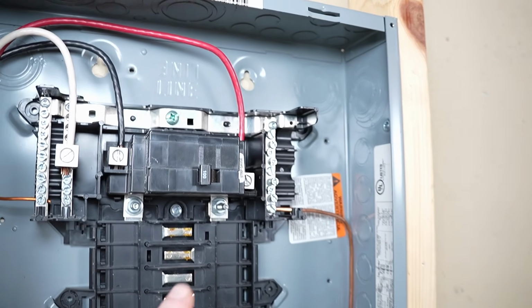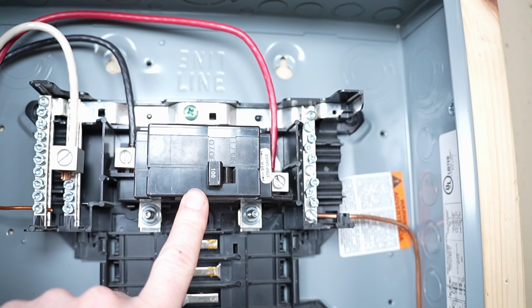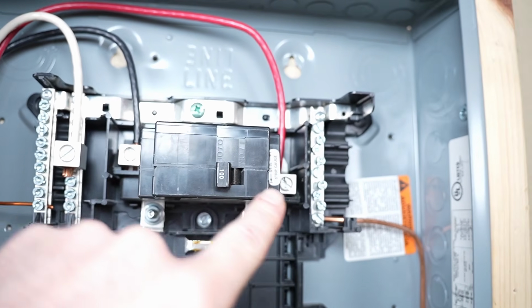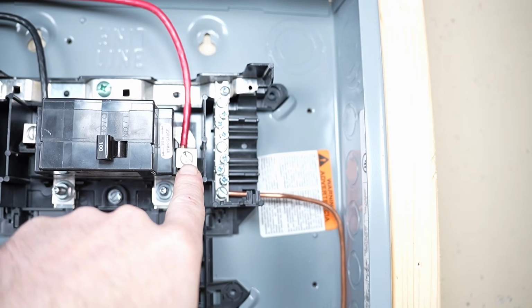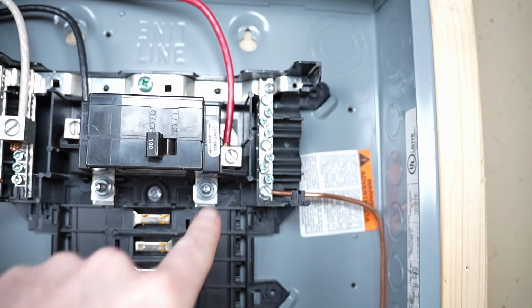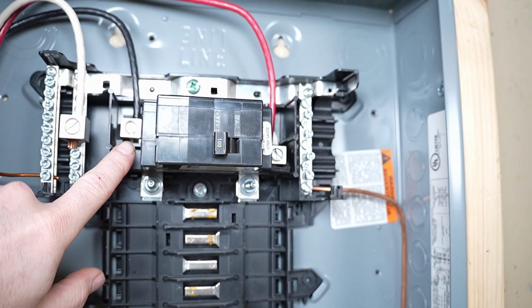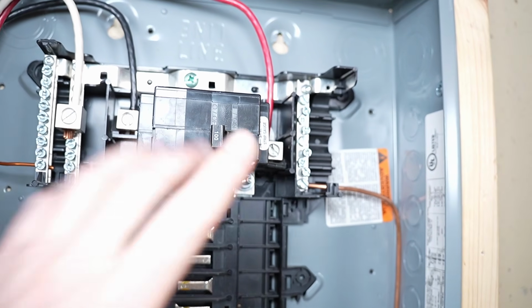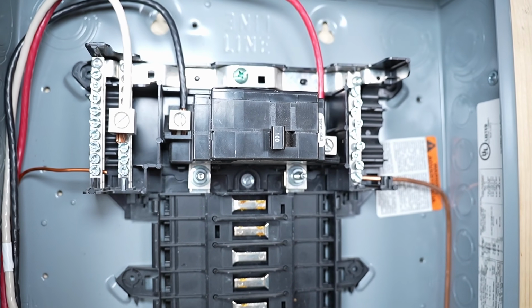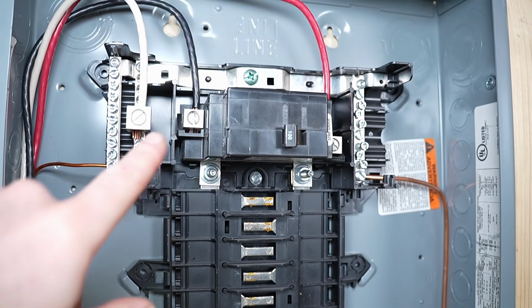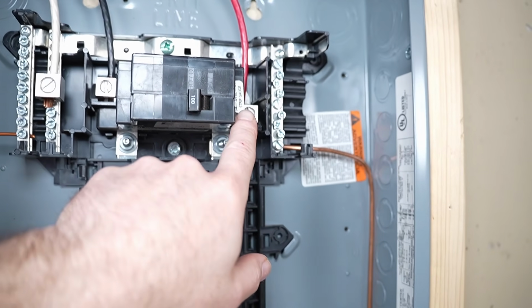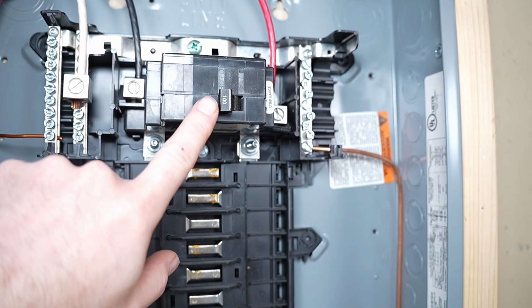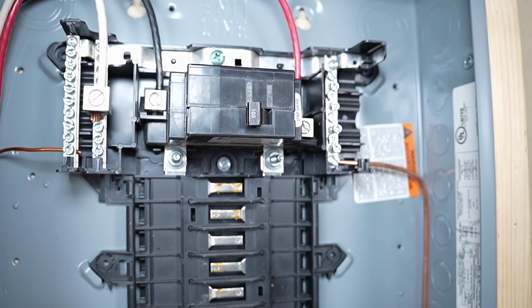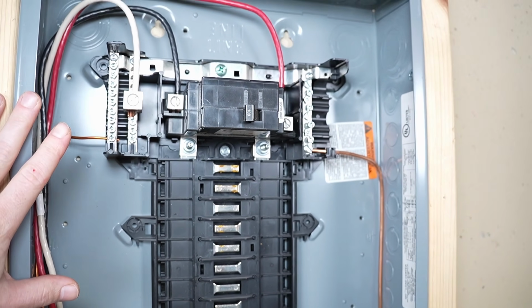In the real world, even if you flip this circuit breaker off, these lugs right here will always be live, and there is no way to turn those off. A lot of modern panels have covers over these lugs, which is fantastic, but many existing electrical panels still don't have covers on these lugs. So just because you turn the main breaker off does not mean everything in this panel is dead.